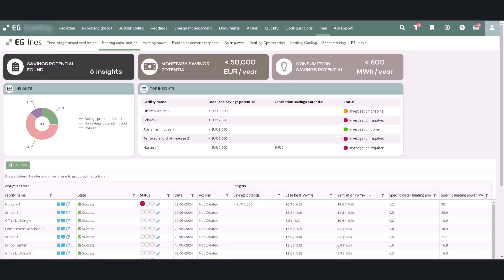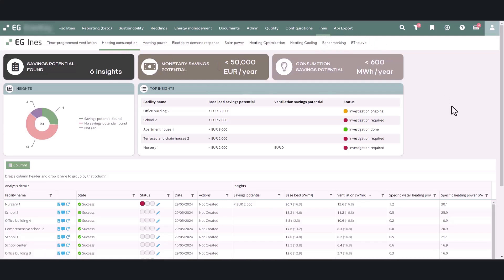Heating consumption analysis divides the facility's heating consumption into three parts: ventilation heating, domestic hot water heating, and base load. In order to work, the report requires the following measurements and basic building data: hourly district heating measurement, building type, surface area, volume, and construction year.